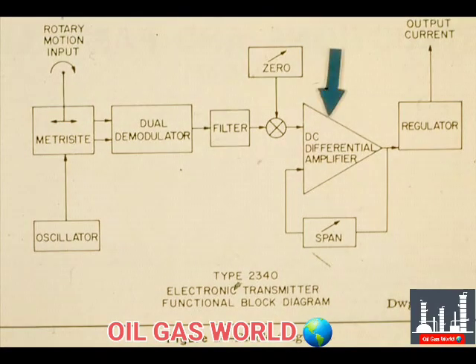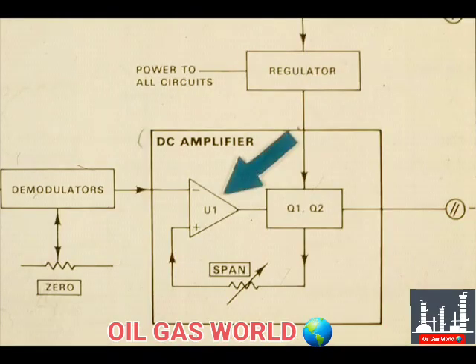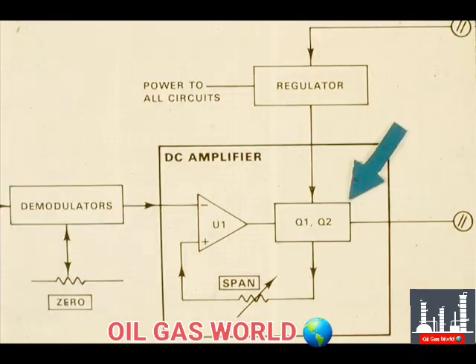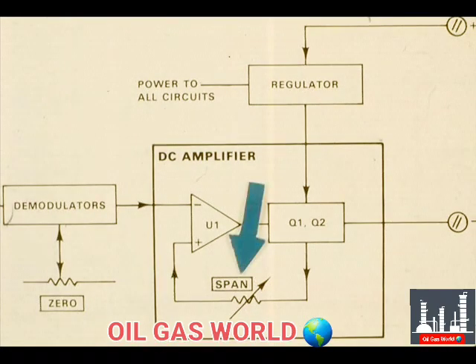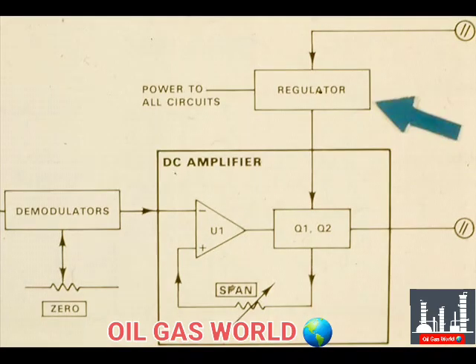The DC voltage output of the demodulators goes through a filter to dampen the effects of process turbulence. The filtered demodulator output then goes to the DC amplifier. The DC amplifier consists of U1, a differential amplifier, Q1 and Q2, which are current controlling transistors, and the span adjustment. The regulator supplies and maintains the constant operating voltage required for the various circuits in the transmitter. For this transmitter, the regulator maintains 10.8 and 6.4 volt supply voltages.